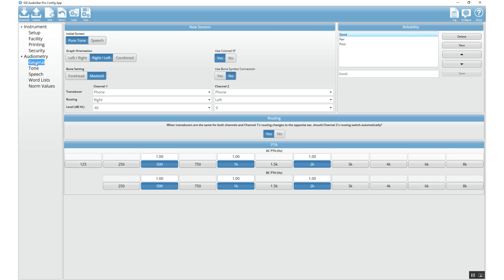Upon first glance it doesn't look that different because we still have all of the features we had before, but if you look closely at the pure tone average you will see that there are little spaces above the selected frequencies that contribute to the pure tone average, and we can actually change those values. For example, if I wanted to add my 1000 Hz two times I can do that — now it's weighted toward the middle. If I wanted to weight it a little heavier in the high frequencies I could do that, or add another frequency with an individual weighted value for each one of those pure tones contributing to the pure tone average.